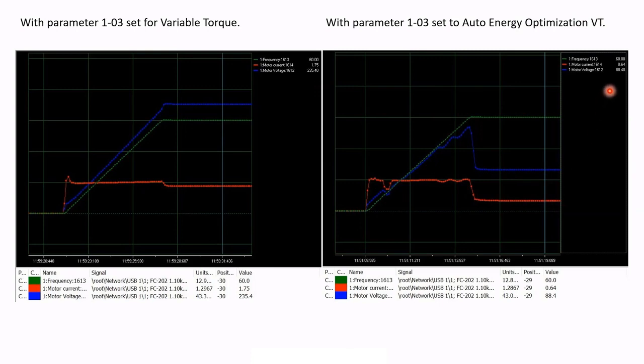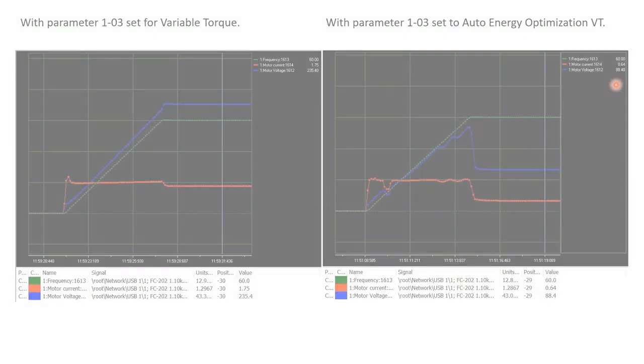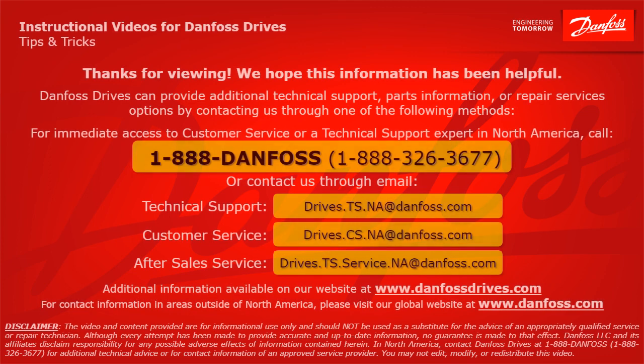This motor is running at 60 Hz and the motor voltage is only 88 volts — that's how lightly loaded it was. That is automatic energy optimization. I hope this was helpful for you. Thanks for listening.